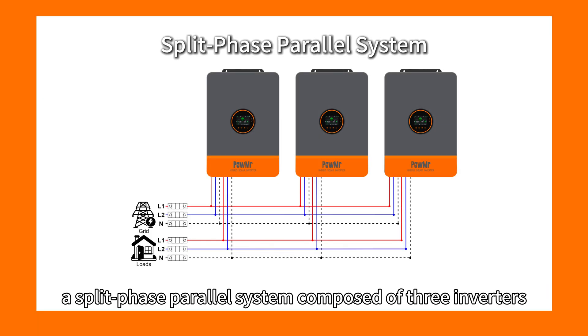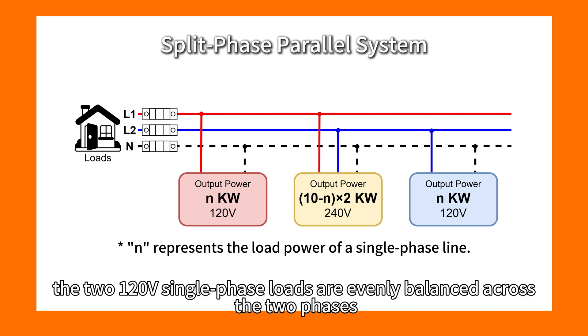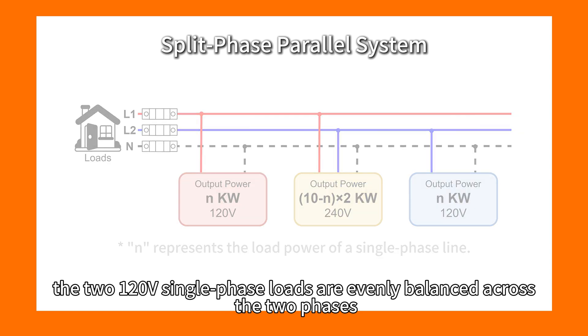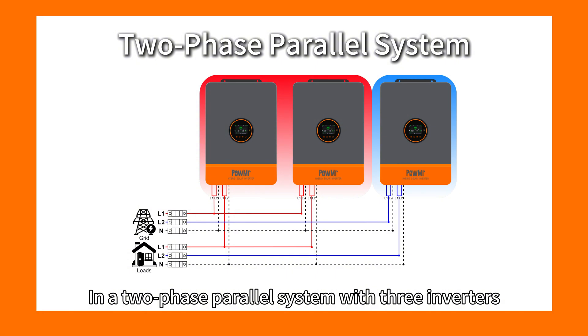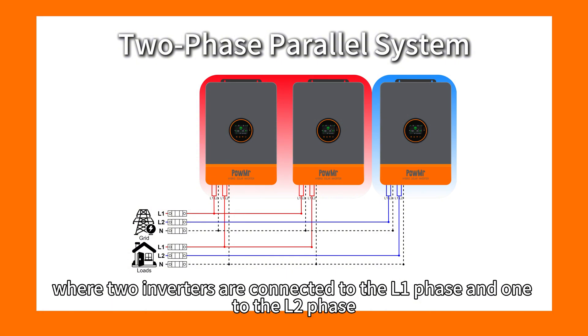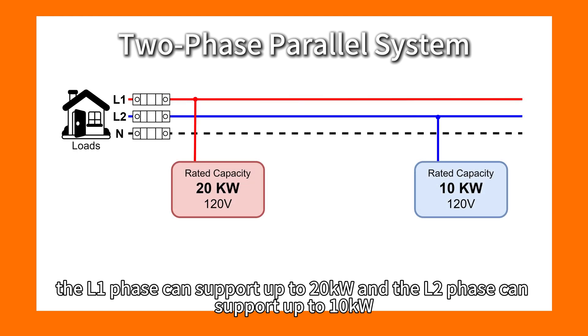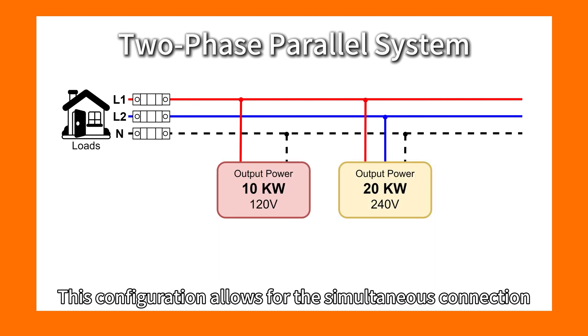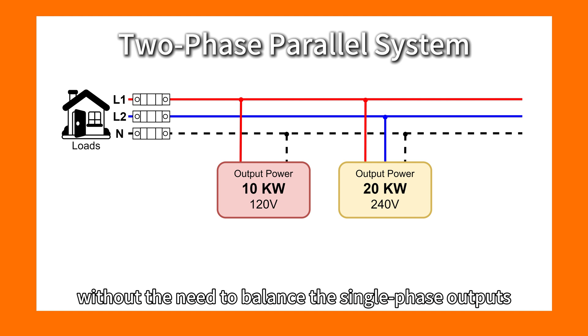For example, a split-phase parallel system composed of three inverters is ideal for scenarios with two 5kW 120V single-phase loads and one 20kW 240V split-phase load. The two 120V single-phase loads are evenly balanced across the two phases, while the remaining capacity from both phases supplies the 20kW split-phase load. In a two-phase parallel system with three inverters — two on L1 and one on L2 — L1 supports up to 20kW and L2 up to 10kW, allowing simultaneous connection of a 20kW 240V split-phase load and a 10kW 120V single-phase load without needing to balance the single-phase outputs.